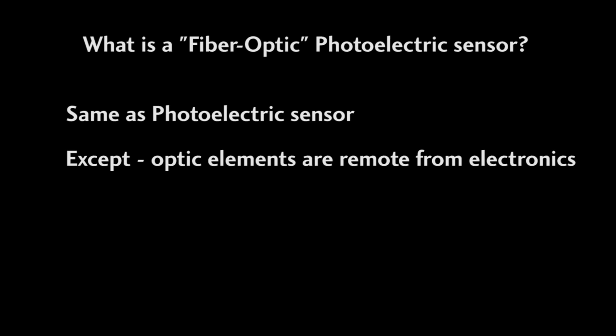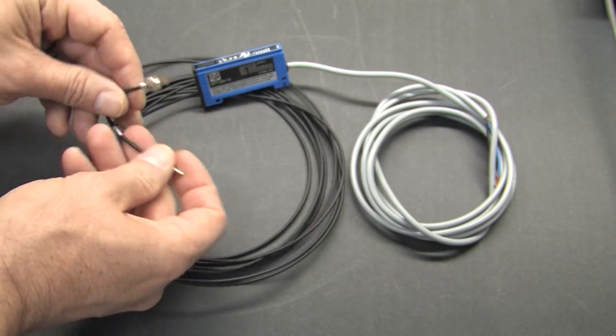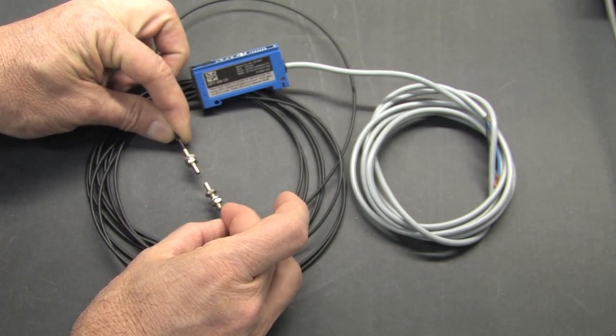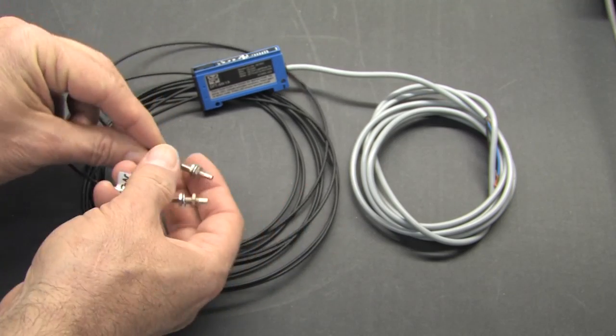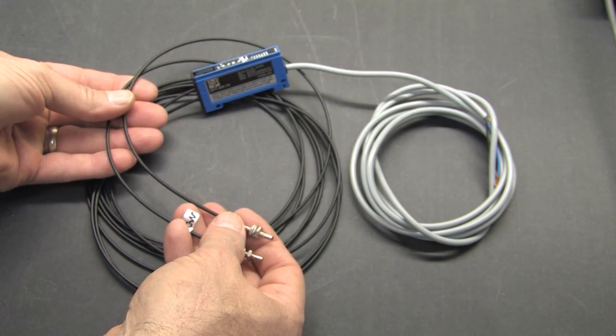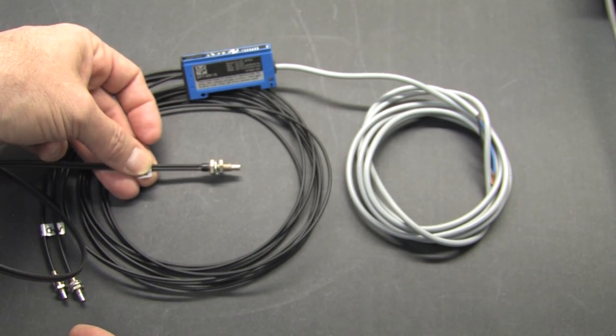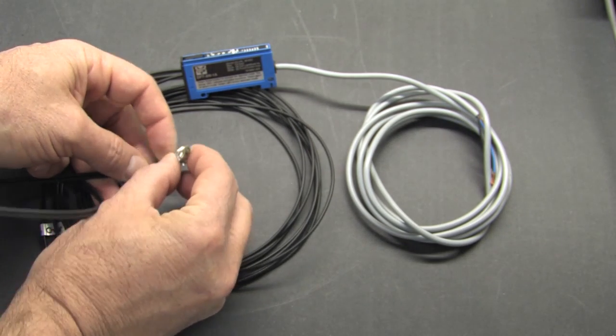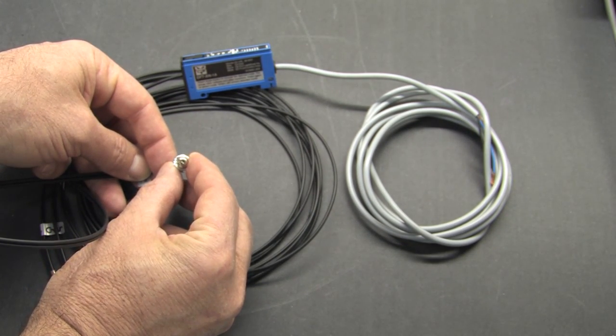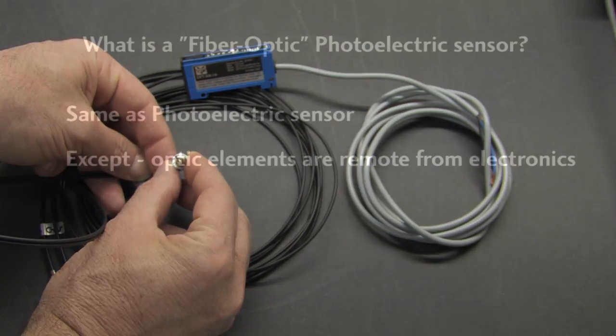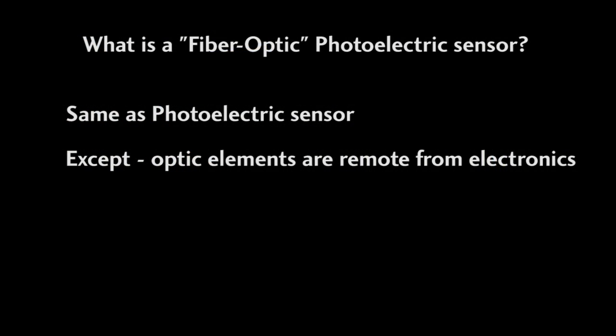Fiber optic photoelectric sensors are basically the same animal as regular photoelectric sensors. The main difference is the optics are separate from the electronics. In this through beam sensor example, you can see the two optics heads which feed back to the sensor electronics through these fiber optic cables. Here is a reflective sensor head where both optics are in one head. Again, it's the same photoelectric sensor, the optics have simply been remoted from the electronics.